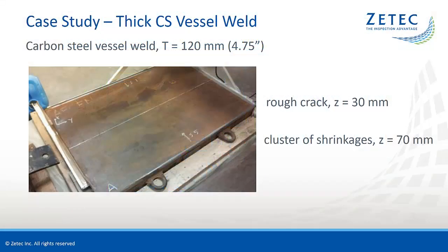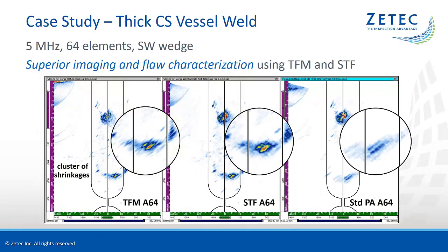The next case study explores the potential of advanced focusing techniques on thick carbon steel vessel welds, from 3 inches and up. Code-compliant phased array UT and TOFD can provide adequate detection, but characterization of deeper indications can sometimes be challenging. The considered specimen is a thick carbon steel weld containing real flaws — a rough crack and a cluster of shrinkages located at different depths in the weld.